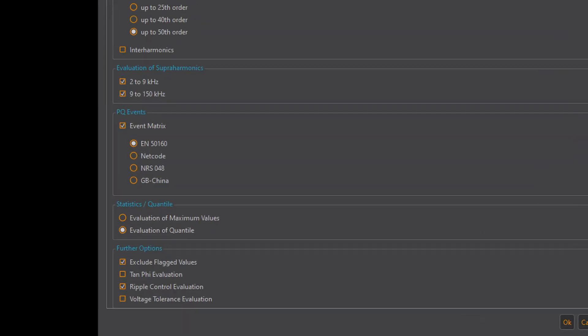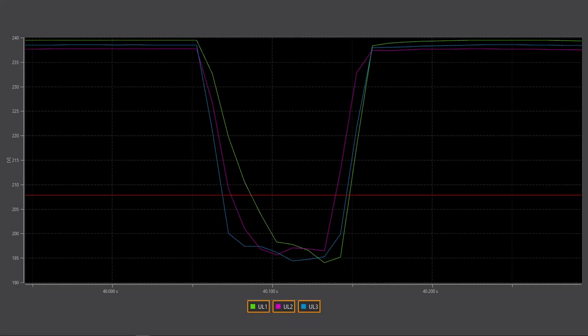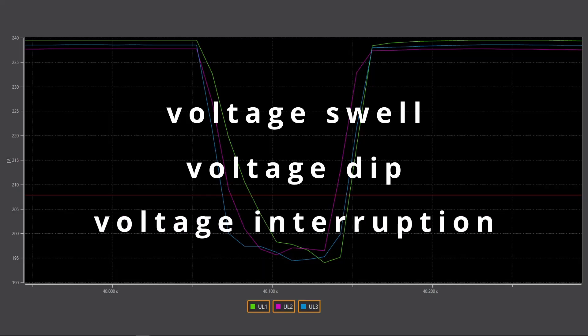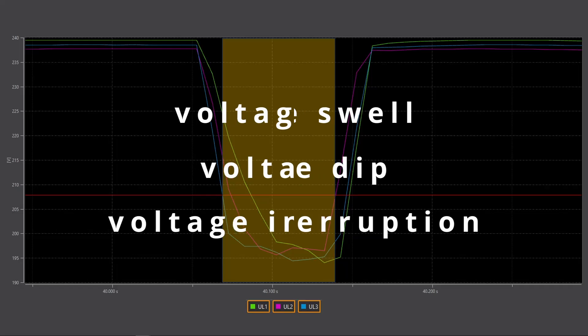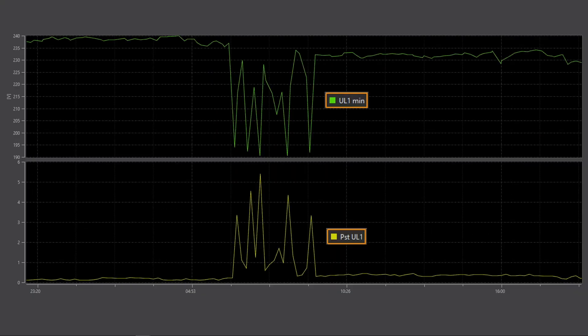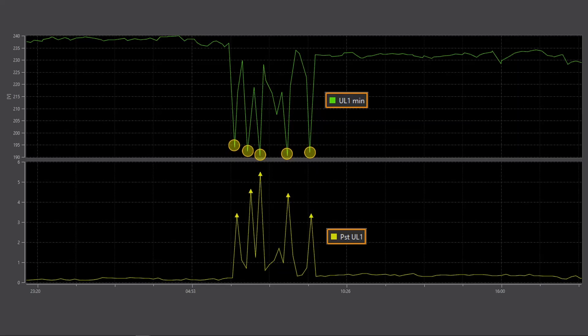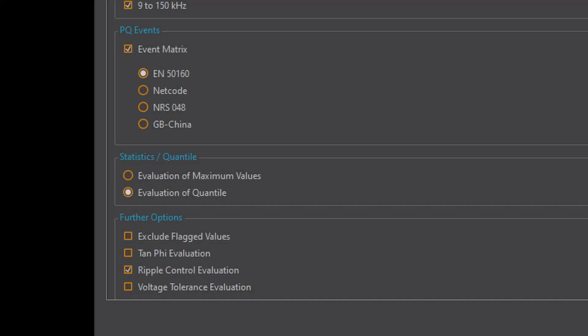The main purpose of flagging is to avoid counting power quality events twice. Unpredictable events such as voltage swells, dips or interruptions automatically flag all recorded measurement data for their entire duration. A measurement variable determined from this data such as the flicker may not be a real flicker at all but actually a voltage dip. Thanks to the flagging concept I can now decide in WinPQ Mobile whether this measurement data should be taken into account or not when creating the report.